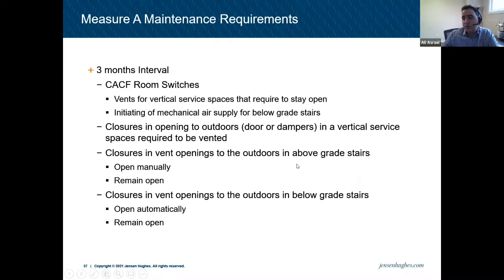Closures in openings to outdoors or doors, if you have doors or dampers in vertical service spaces that are required to be vented, we need to test them every 3 months. These are based on, again, the National Fire Code. Closures in vent openings to outdoors and above grade stairs open manually and they remain open.